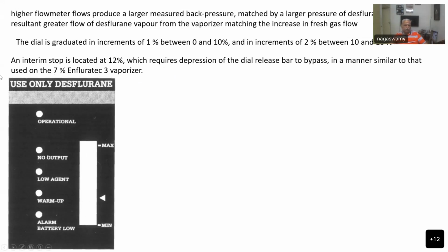So these are all the front panel lightings which you will see. There is no output light alarm, low agent level, warm up alarm, battery low. So all these four displays are LEDs and one is operational. So 5 LED lights are there. Some examiners are fond of asking how many LED display lights are there in the Tec 6 vaporizer. So remember there are 5: alarm for battery, low battery, warm up, low agent, no output, and when it is operational, this green light only should burn and all the other four should not be on.